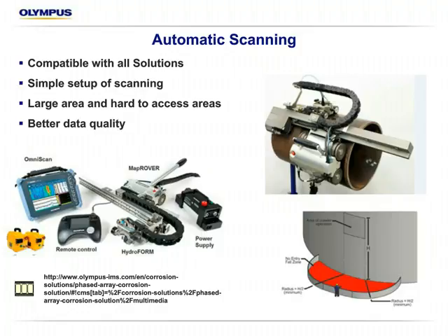So obviously these become a huge benefit for a few reasons. If it's a hard to reach access area, a steerable, drivable, or some way to get to the area of inspection, especially if you can't scaffold and get a person up there to take more manual readings. But it also has much better data quality when we automate. If we can control the exact speed it's always moving, we can control all those types of things, we're going to get a much better data quality as well.